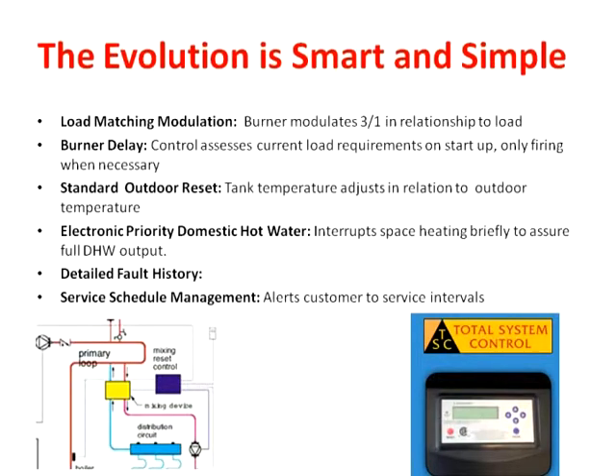This has detailed fault information. You'll find that all your fault information is in English. It's much more expansive and detailed relating to what the system is doing. You can see all the different temperature probes, including going to and from space heating, to see what's going on in the system. It also has service schedule management. If you wish, you can put in parameters either by run hours or by date to have a notice pop up on the screen suggesting that it's time for service on the unit. I was just pointing out that this system control is controlling these two pumps in an intelligent manner that we normally would have seen with a lot more piping and complications.